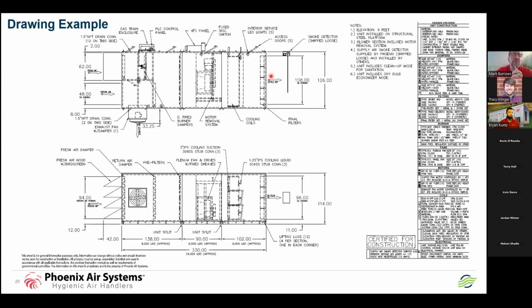For the most part, these are going to be installed on structural steel. There are situations where, to save cost, people would put these on roof curbs. We're not big fans of these on roof curbs when the room is probably 40 or below. Warmer rooms are one thing, but we've got to be really careful that we don't have any condensation problems beneath that unit through the curb. So you've got to be really careful on that. So again, for sake of argument, we probably put these up on structural steel.